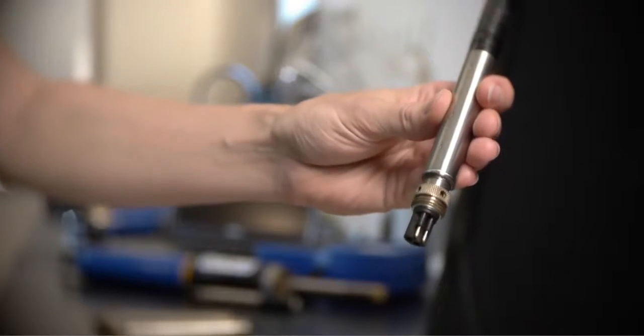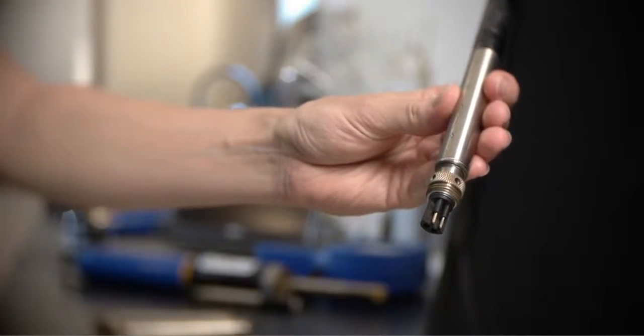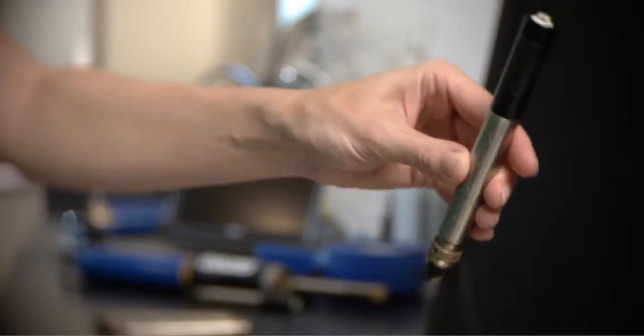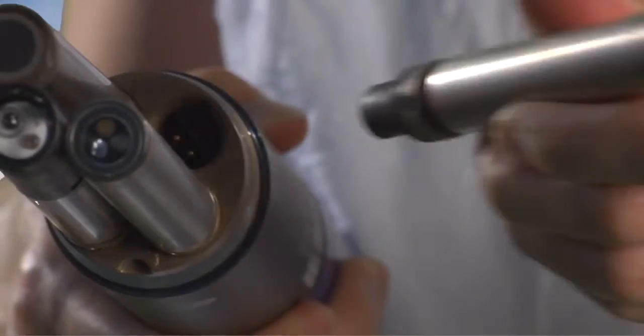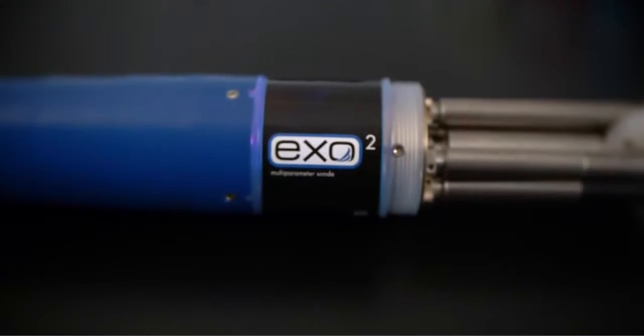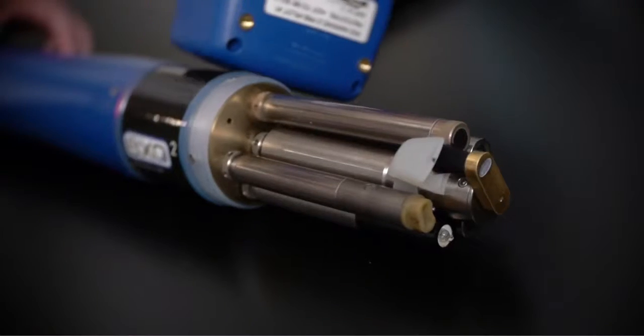The new EXO sonde has wet mateable connectors, which for a lot of our customers using the 6 series, they had issues with getting moisture calibration solutions into the ports, which can sometimes destroy those and make you have a bulkhead replacement. So you can put any sensor in any port and the instrument wakes up and automatically recognizes that sensor. It not only knows what sensor is plugged into it, it knows the serial number of the sensor, it knows when it was last calibrated.